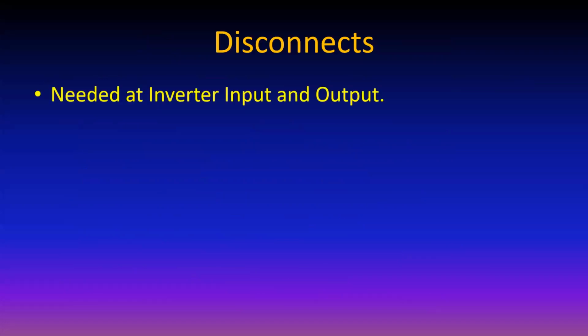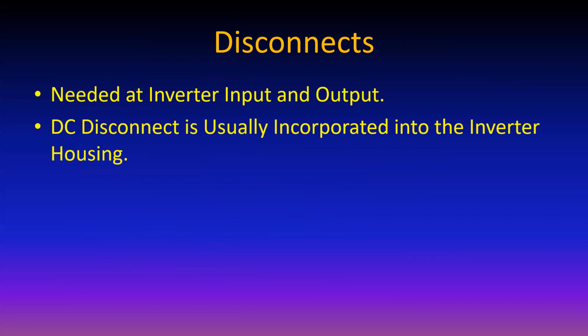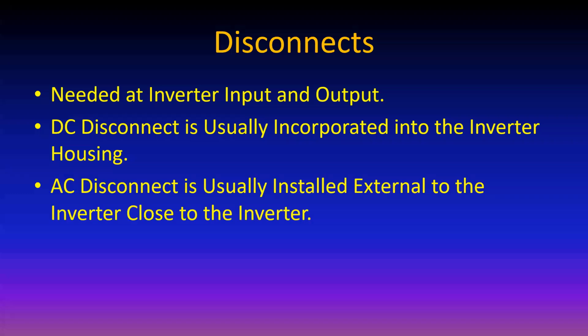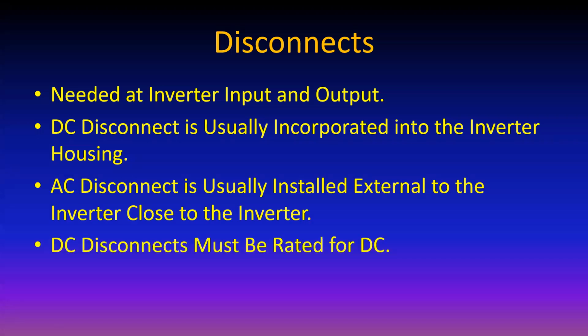Disconnects, yeah, you need that, the inverter input and output. The input generally is a part of the inverter. The output is oftentimes a separate disconnect, but hopefully within sight of the inverter, because that's the whole idea, for maintenance purposes. And have to keep in mind that the AC disconnects are rated for AC and the DC disconnects are rated for DC.